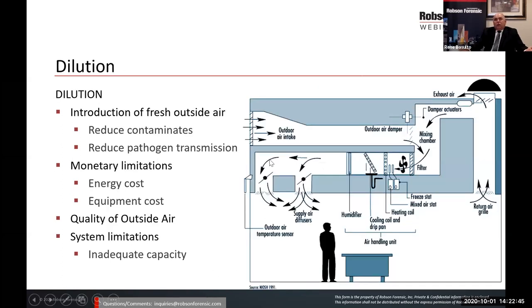So the first solution, and I touched on it briefly, was dilution. And again, if we bring in all this outside air, we just dump it straight into the space and we exhaust all of the indoor air out, it'd be great, assuming you have decent outdoor air to begin with, right? That's another topic we'll talk about a little bit. So that would completely reduce the contaminants and reduce the pathogen transmission, but it has certain limitations.